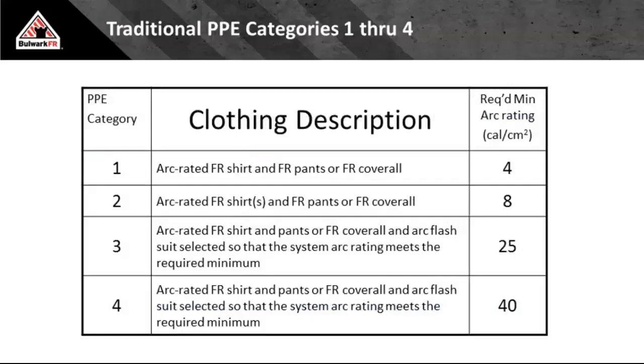This is what you need to understand. If I have 3 calories of incident energy, that's a Cat 1 box. Why? Because it's under 4 calories. That means I have to wear 4 calories or more protection. Cat 2 box: if my incident energy says 7 calories, that's a Cat 2 box, and I have to wear 8 or more, and so on. Cat 3, 25 or more. Cat 4, 40 or more. This on your right is how much more protection you need so that you can work on the appropriate category.